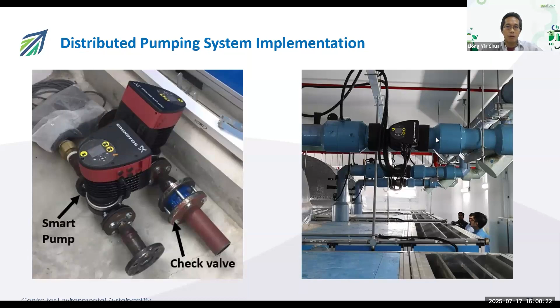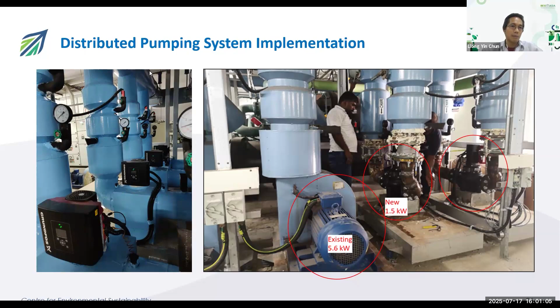And you can see that this pump is quite small, so we don't need much support. We can just have an inline pump that is joined on the pipe, along the pipe itself. And for the primary pump, you can see in this picture, this is the existing 5.6 kilowatt pump. And with the Grundfos pump that we install in line, we actually just reduced to 4 sets of 1.5 kilowatt from 4 sets of 5.6. So you can see this is after retrofitting. It's very beautifully done, I would say. It's all in line, and this pump is very small as well. Because the existing pump location is here, we still put the pump in the middle. Otherwise, this small pump can probably go at the top there and just go direct.